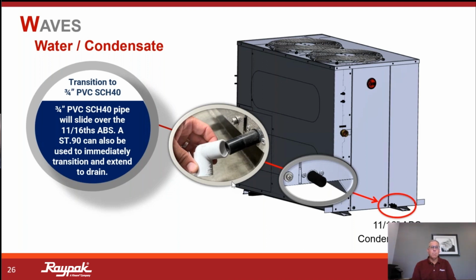All of them would get legal situations going on where the contractor had used the wrong solvent cement. For example, Christy's Red Hot Blue Glue is designed for PVC. And you would have people say, oh, it's hot enough chemically, I'm going to use it for ABS. I'm going to use it for CPVC. I'm going to use it for polypropylene. No, it's not recommended. And the piping manufacturers will take those failed joints, cut them open, find out what glue is used, and then it goes to the attorney. So what I would say to the contractor is, find an approved joining method that meets the piping manufacturer's requirements and the plumbing code.